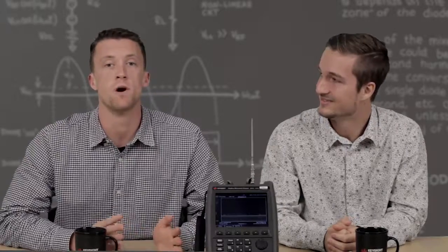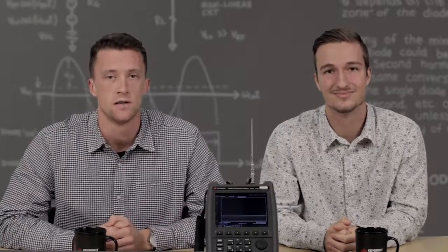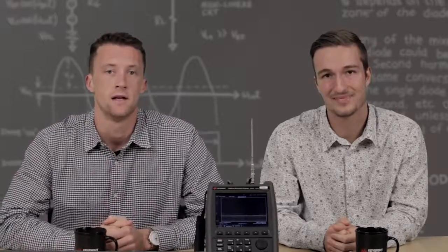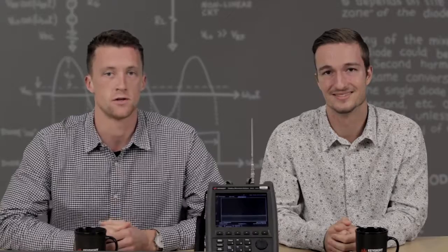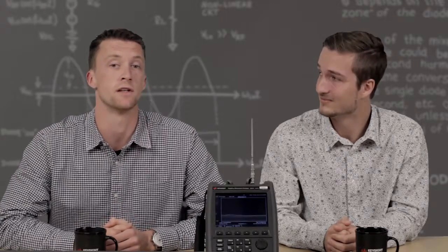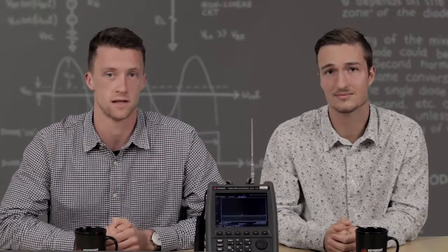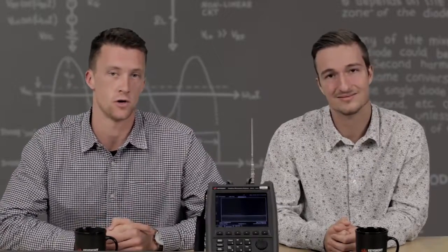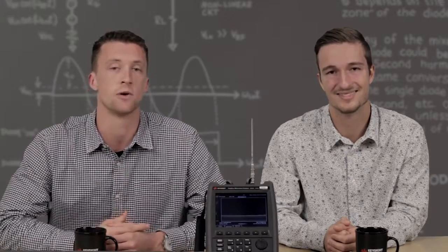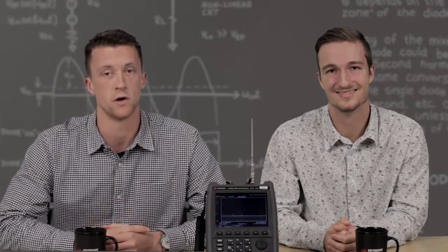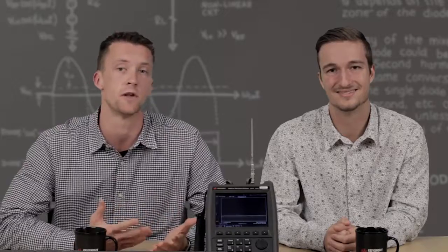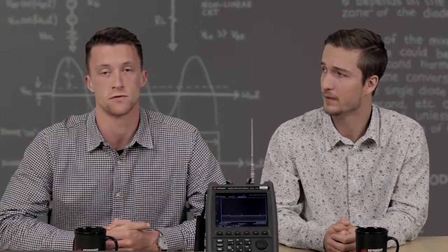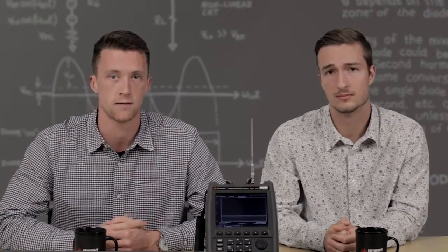And there are actually three modes of real-time operation on the FieldFox. The first one, real-time spectrum, essentially shows the same thing that the traditional SA mode does. It shows amplitude versus frequency. The only difference is that it is showing it instantaneously in real time. The second mode, called density spectrum mode, shows amplitude versus frequency and frequency of occurrence, which makes this mode very useful for showing signals that fall on top of each other. The third mode, spectrogram mode, shows amplitude versus frequency and how these occur over time.